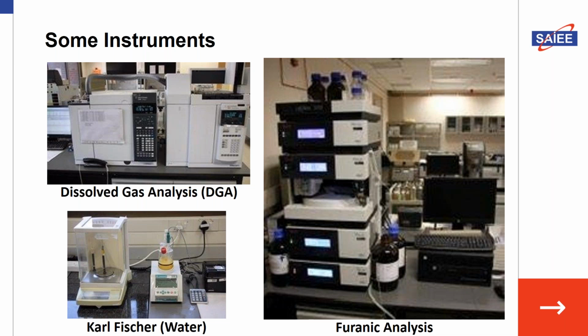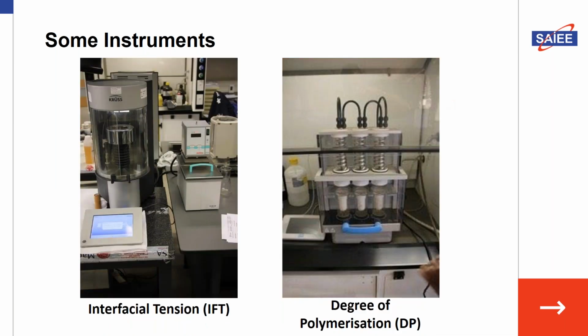You can see dissolved gases in the lab, replacing the instrument you saw in the previous slide. At the bottom is a Karl Fischer instrument, which tells you water content, and on the right is furanic analysis, a proxy of the aging of the paper found in the oil. The next two instruments show interfacial tension, a characteristic of the oil indicating whether it's maintaining its properties, and on the right-hand side is degree of polymerization, a test done on paper samples, paper being the insulation medium covering the windings in a transformer.